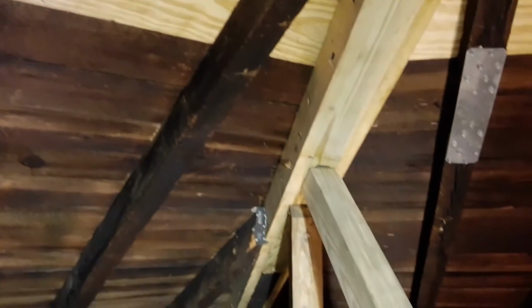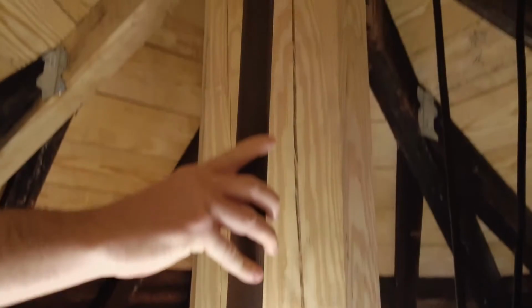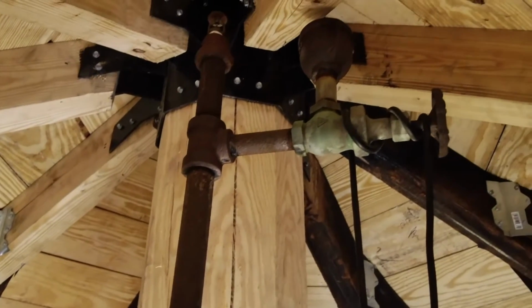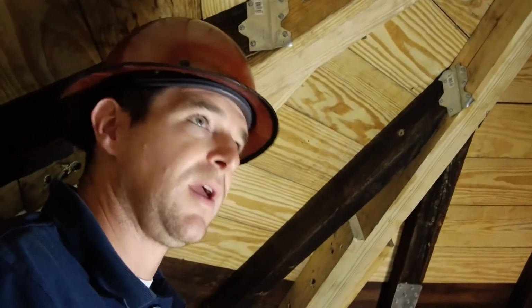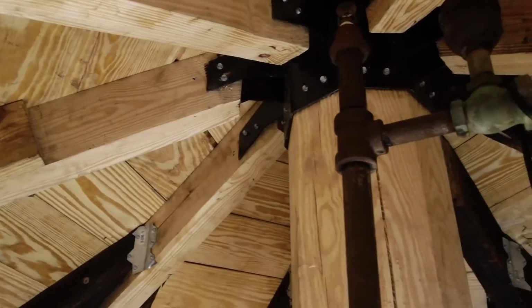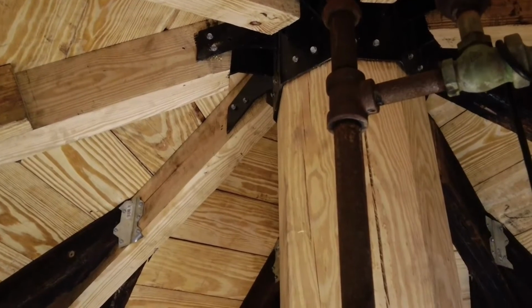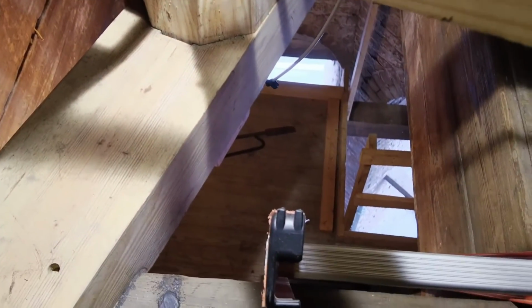And one of the largest complications in the last fire was the inability of water to get to the needed locations during that fire. This sprinkler system right now has no water in it at all. The street pressure pushes the weight of the water up about 70 feet off the ground, and this is about 135 feet off the ground. So about half of this bell tower has no water pressure in it at all, and it never did have any pressure because the city pressure wasn't higher than it is now back in the 60s when this system was put in.